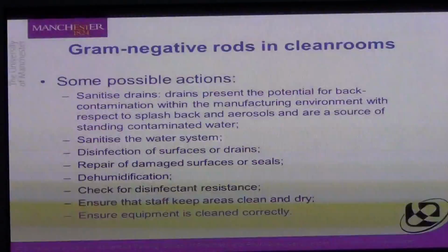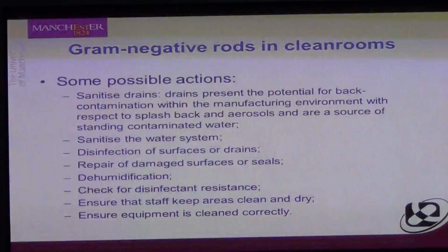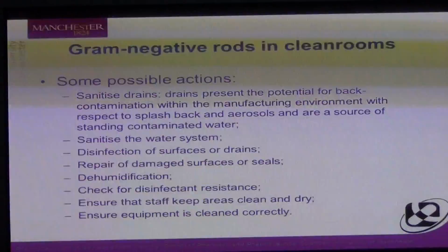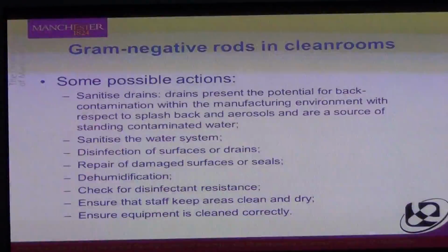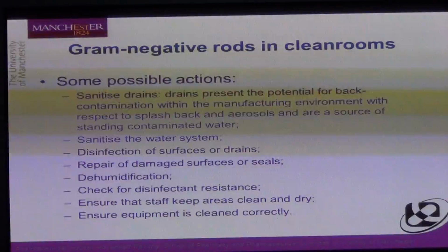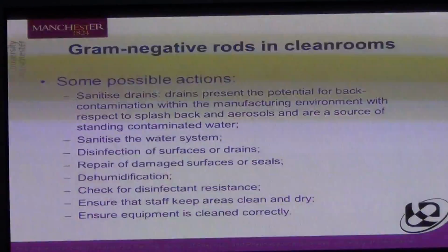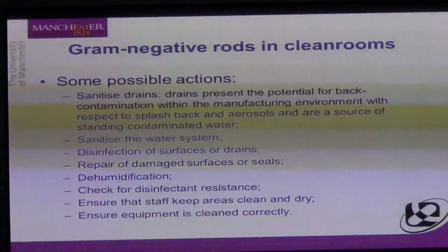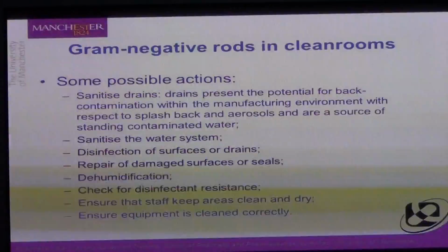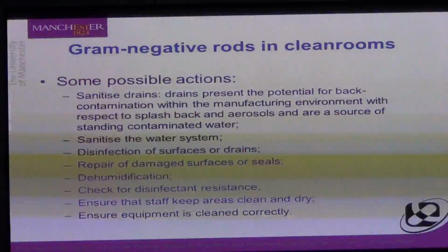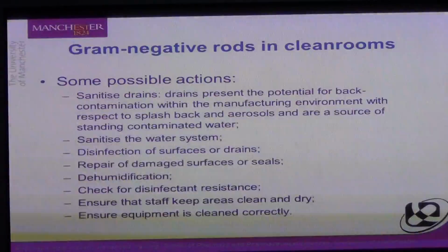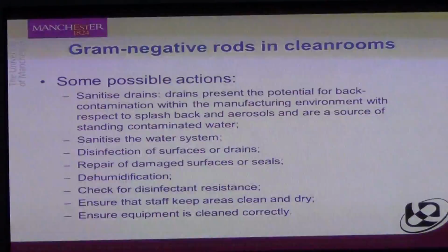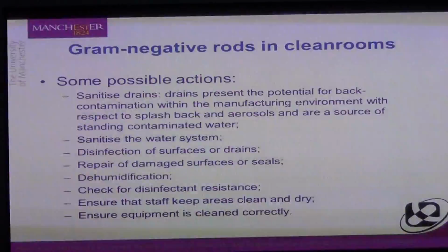In terms of actions to do with these gram-negative rods, you probably want to sanitise your drains or have a look at them. Are you getting back contamination from the drains? Splashback? Aerosol, standing water. If it gets very serious, you find it in your water system, you may want to undertake a sanitisation exercise of your water system. Disinfection of surfaces and drains, damage and replace seals. Maybe you want to try and dehumidify the area. Check your disinfectant resistance. Check that the staff are keeping the areas as clean and dry as possible, and ensure the equipment is cleaned correctly.